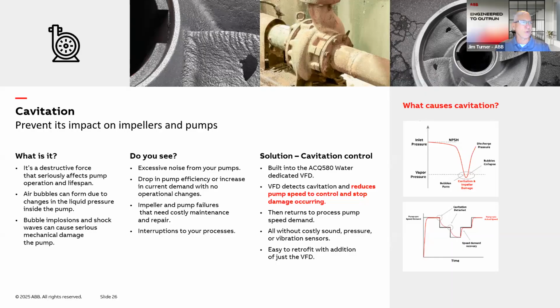It sounds like the pump is grinding or pumping grit or small pebbles through it. The damage to the impellers can be slow over time, or it can happen quickly, depending on the severity and the duration of cavitation. Your pumps will become inefficient or possibly inoperable, due to the prolonged cavitation. Our ABB VFD can detect cavitation. It can be programmed also to respond in a few ways depending on your application.